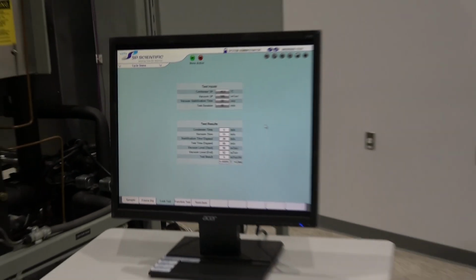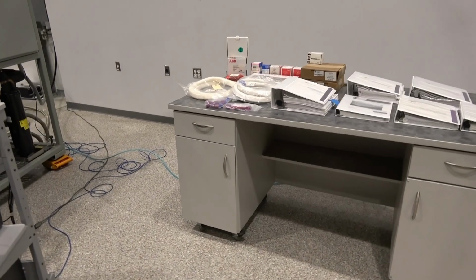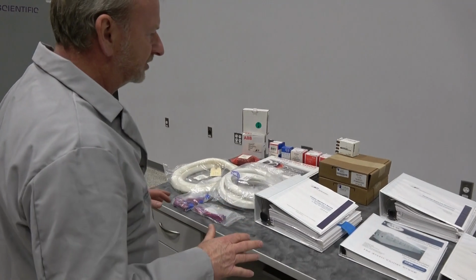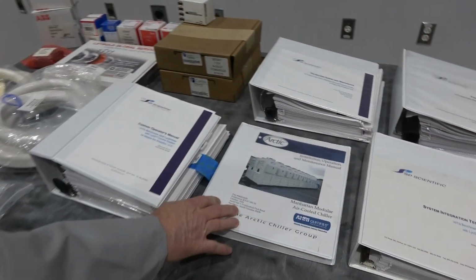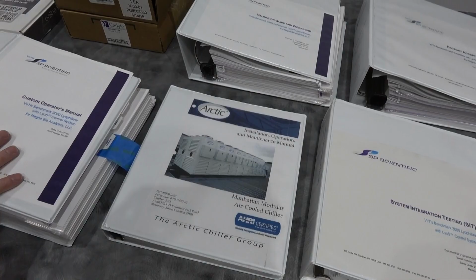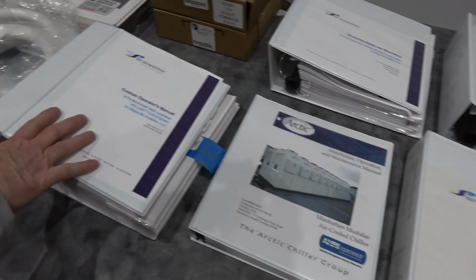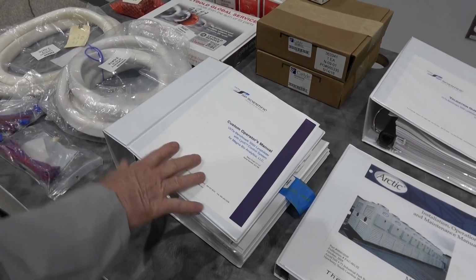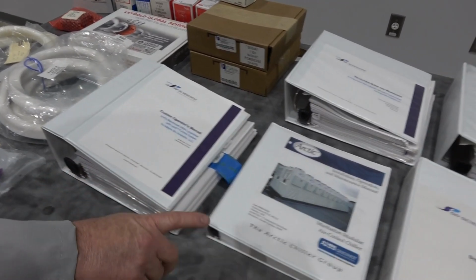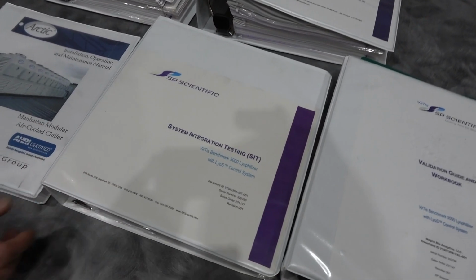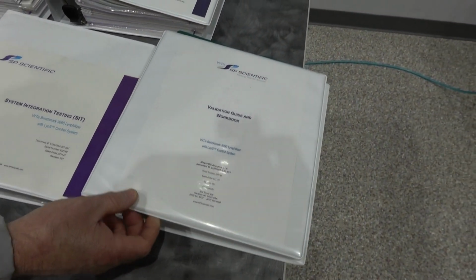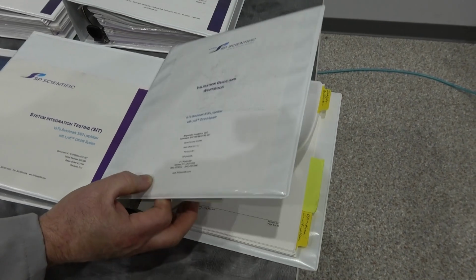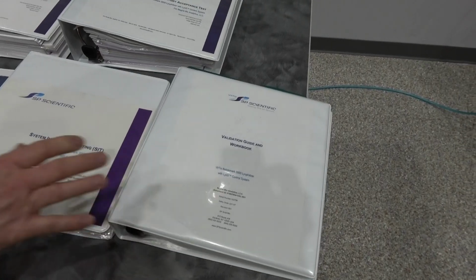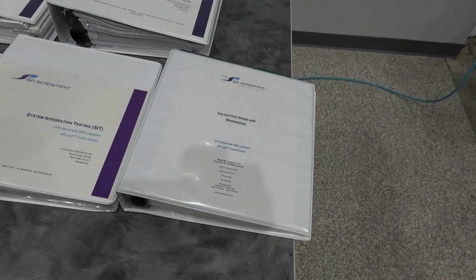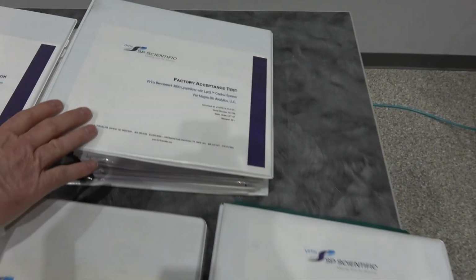Now we're going to just walk over and look at all the documentation. So all the original documentation that comes with the machine, even including the Arctic chiller manual and installation operation manual for the actual Benchmark 3000, and it even has the system integration testing. Then over here it has the validation guide and workbook, so this covers validation, OQ, IQ, which is really important for pharmaceutical grade, especially for clean rooms. And then the factory acceptance test, and the validation guide and workbook over here.